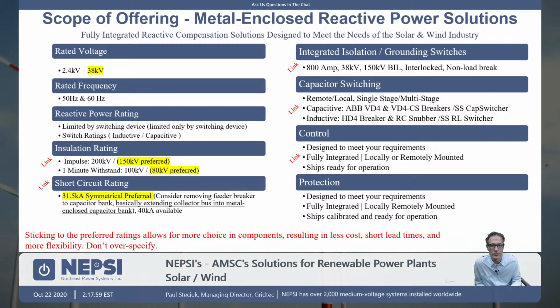It's very typical that we might have 4 stages of 12, like we showed you earlier, or 4 stages of 15 megavars. So they can get quite large, these systems. So remember, reactive power rating is really dependent upon the switching device, and we'll talk about that in a moment. The insulation rating.